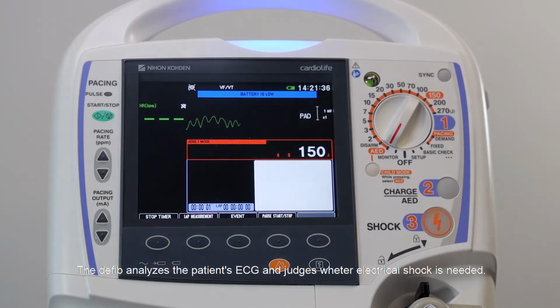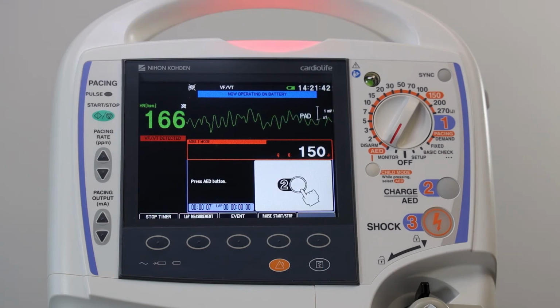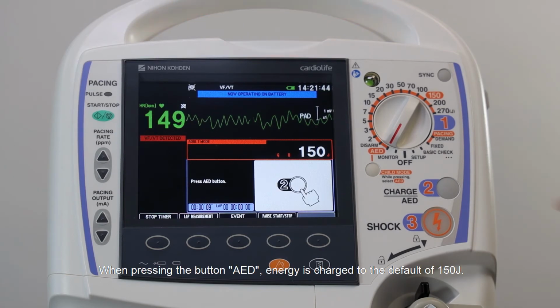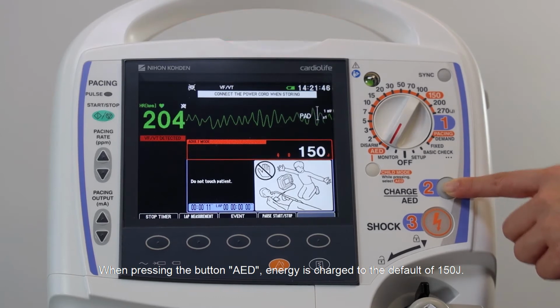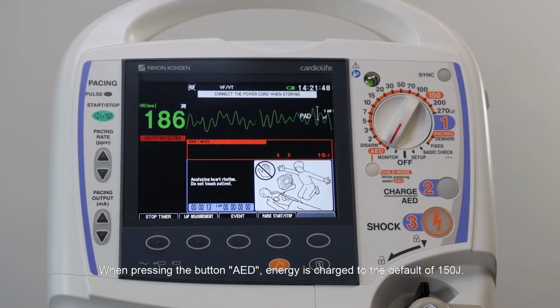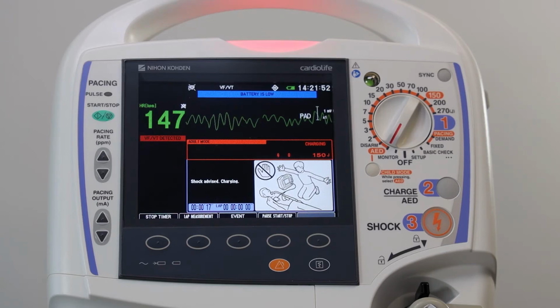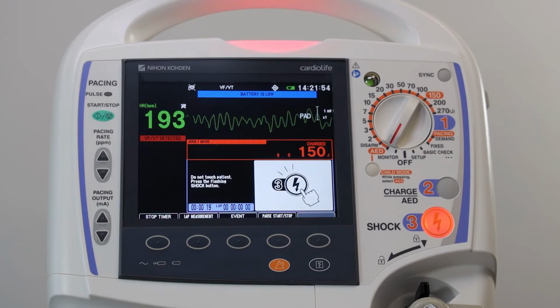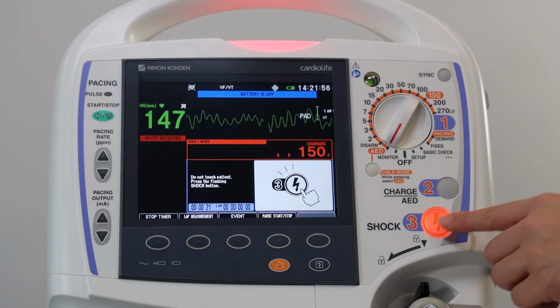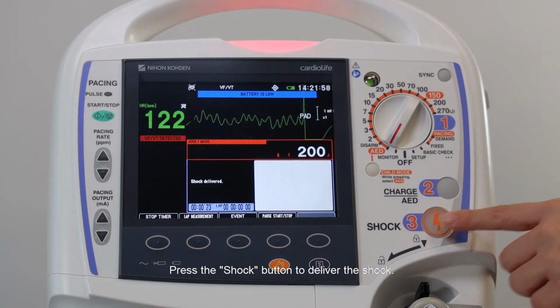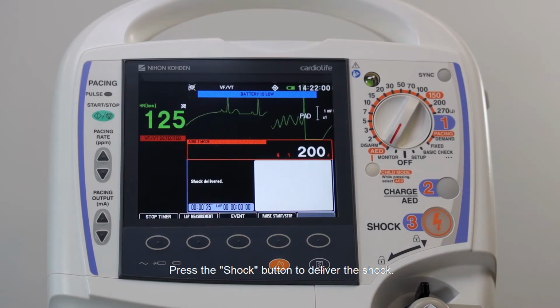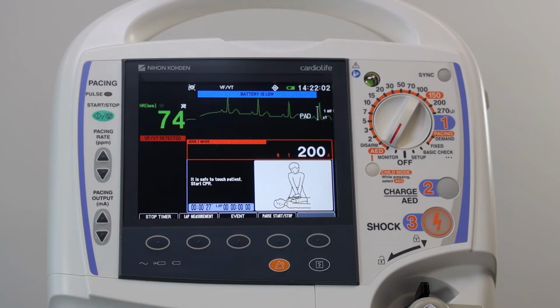The defib analyzes the patient's ECG and judges whether an electrical shock is needed. Press AED button. When pressing the button AED, energy is charged to the default of 150 Joule. Do not touch patient. Shock advised. Charge, do not touch patient. Press the flashing shock. Press the shock button to deliver the shock. Delivered. It is safe to touch patient.